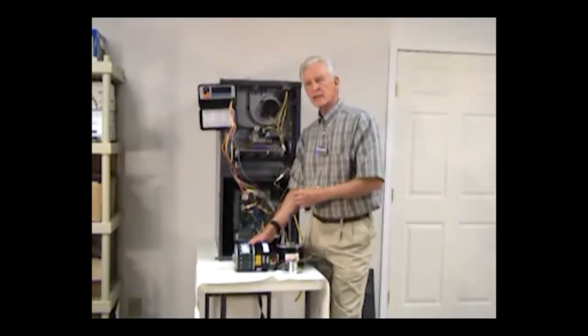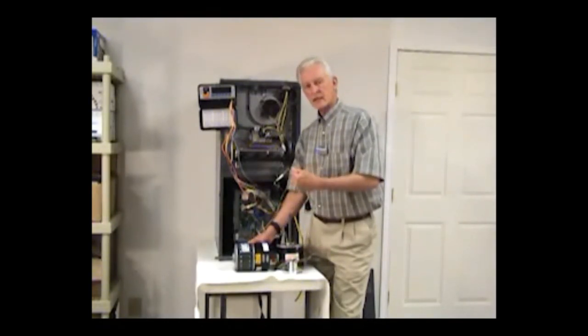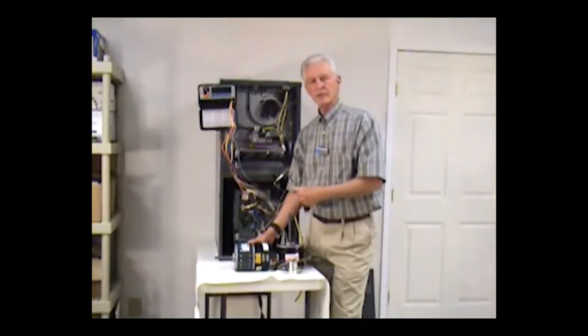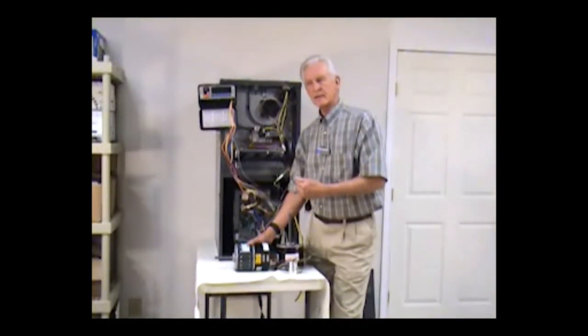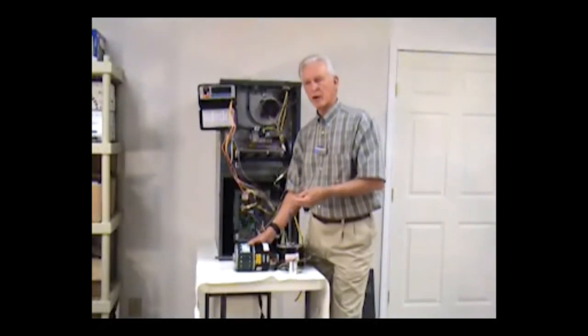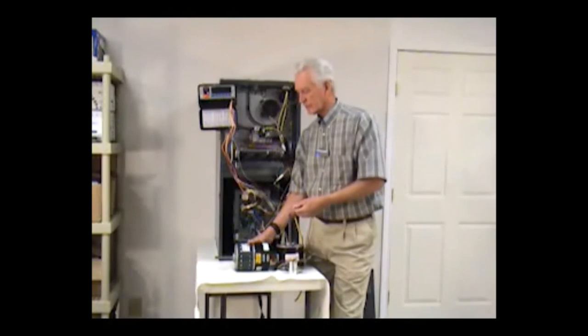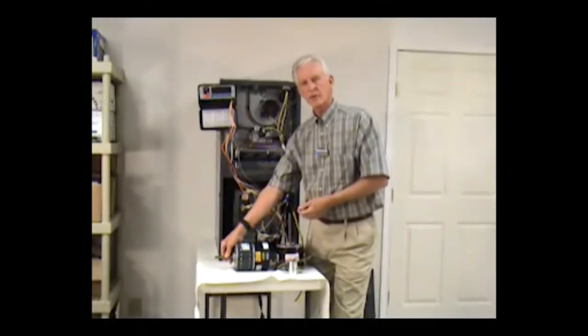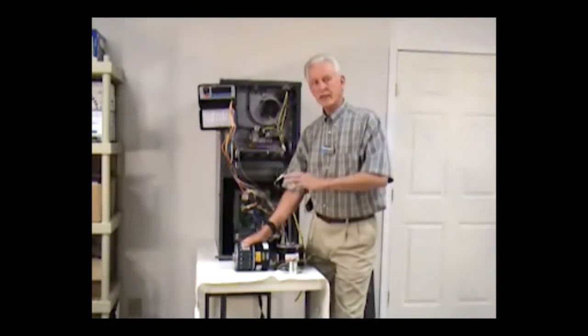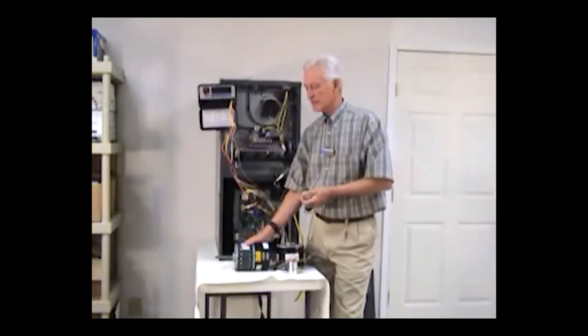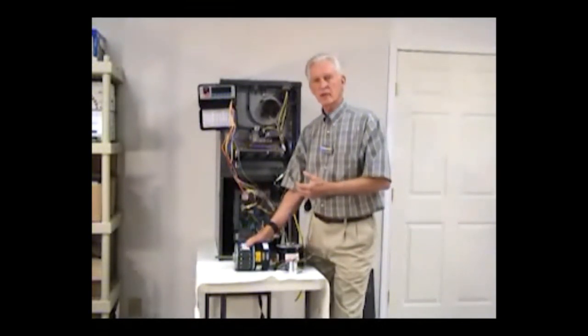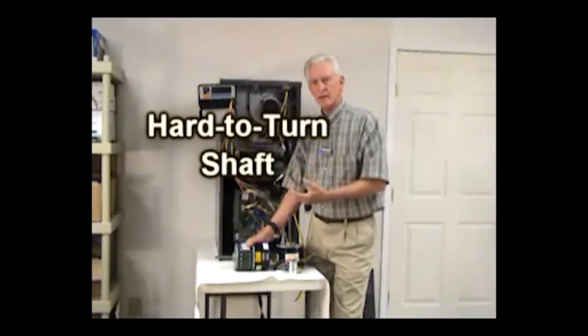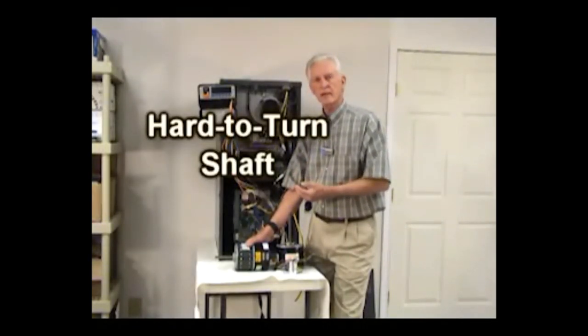Should the occasion come up where an end user has made comment that they have not heard this noise before with their older system and that the current unit is making a bumping sound, and you come as a technician to take a look at it, you've never noticed this situation before where the motor is rocking back and forth from one position to the other, do not condemn that motor because of that situation. That is a normal phenomena that motor goes through to try to figure out which way it needs to go.